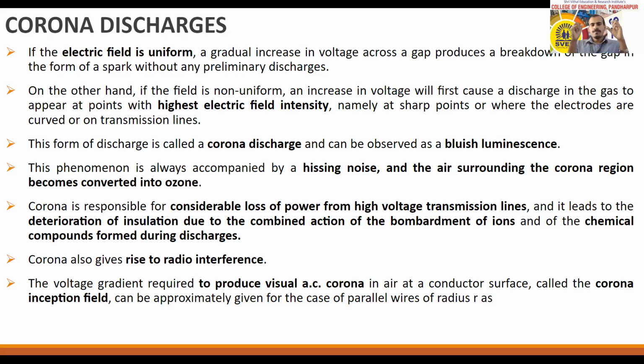Corona also gives rise to radio interference. As we saw in the last lecture, since this conductor's surface is surrounded by corona discharge, if another radio line or telephone line passes nearby, it will spread its electromagnetic field towards that line, and it may get interfered with.